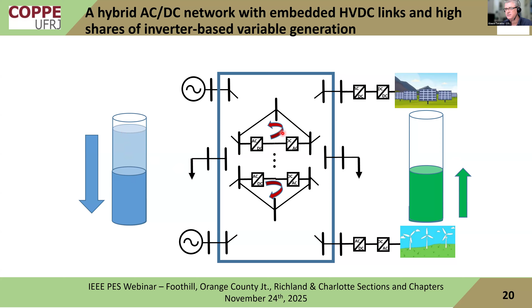just because of this shift in generation. And this is the first time that this was noticed in Brazil, a loop flow, seven years ago. This was published in a Brazilian conference in November 2019. And you can see here at the beginning of the day, this is the wind generation in the northeast. The wind was around 7 gigawatts, around 8:30. This line here is the AC transmission from northeast to southeast. And this blue line here is the HVDC. At that time there was only one HVDC link in Brazil; now we have three, two already in service, and the third one is being constructed.